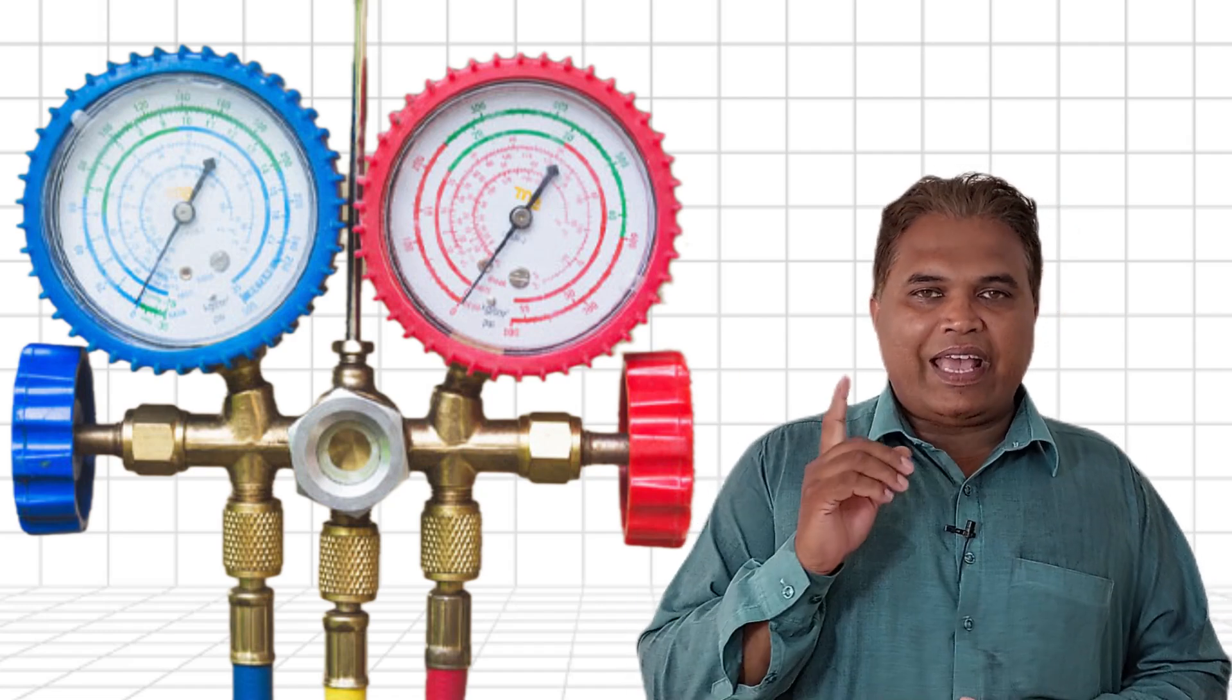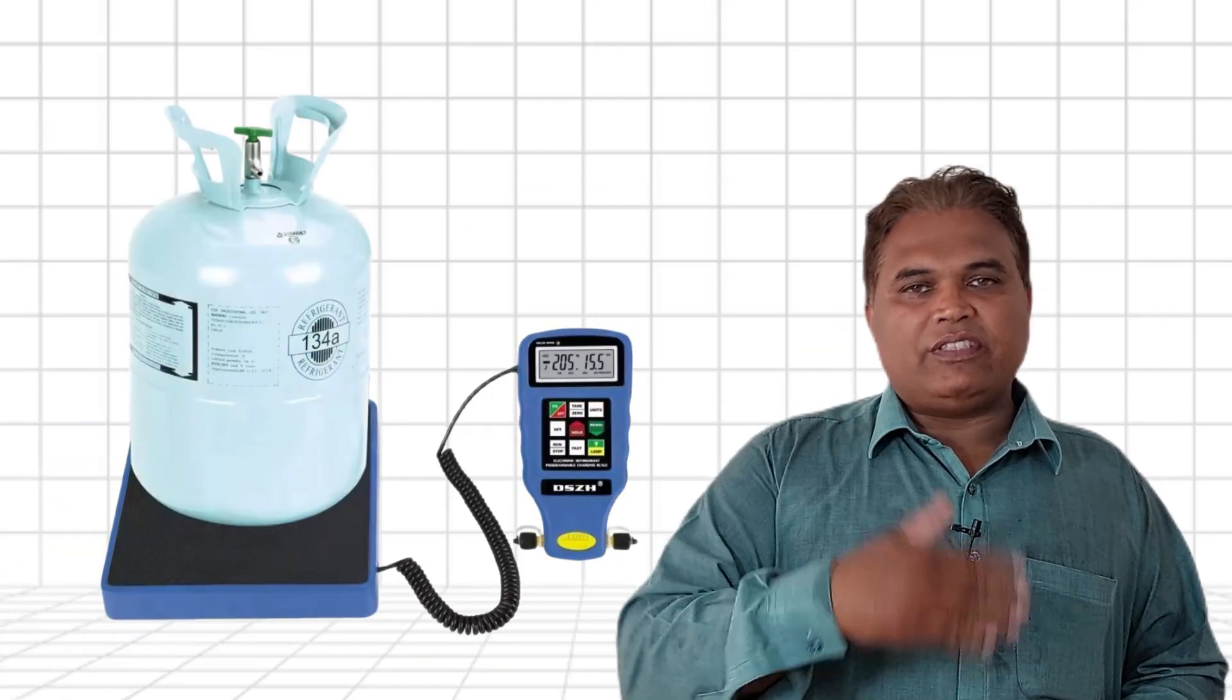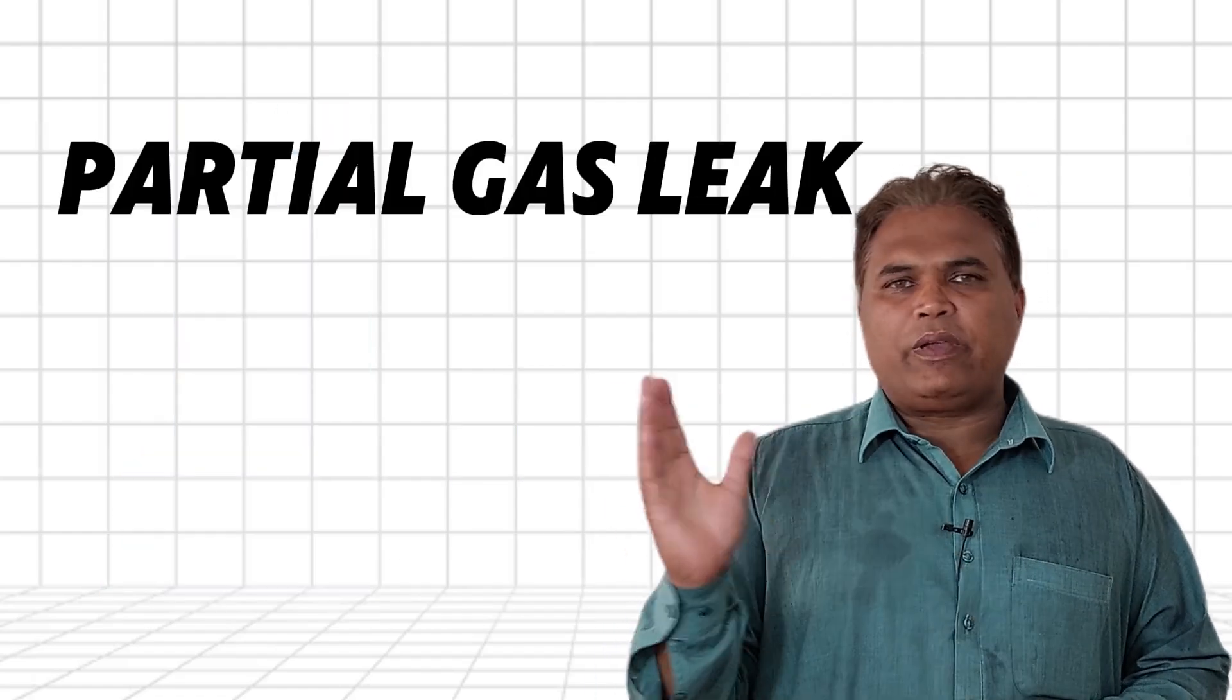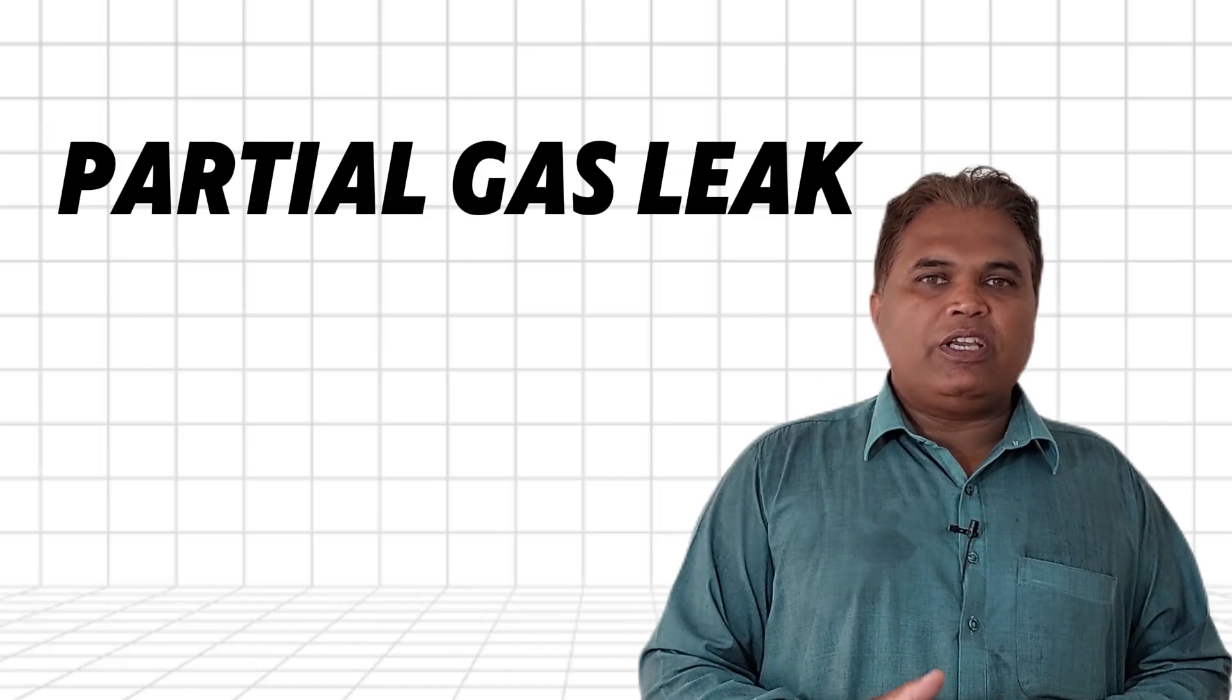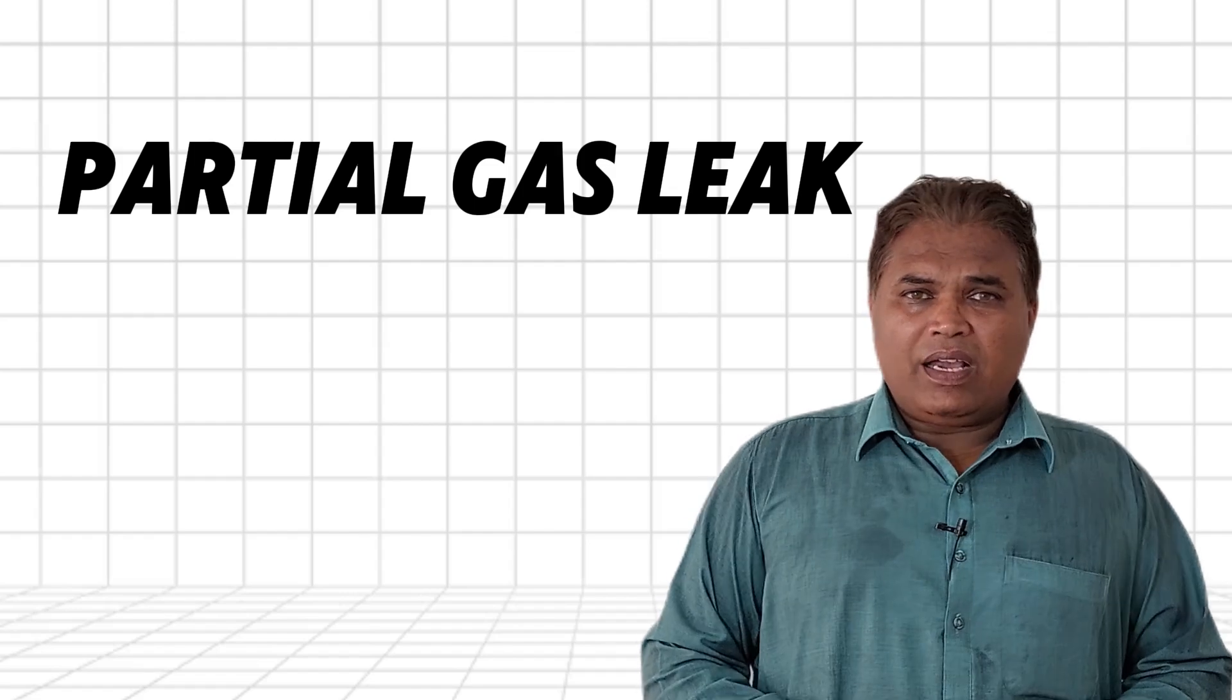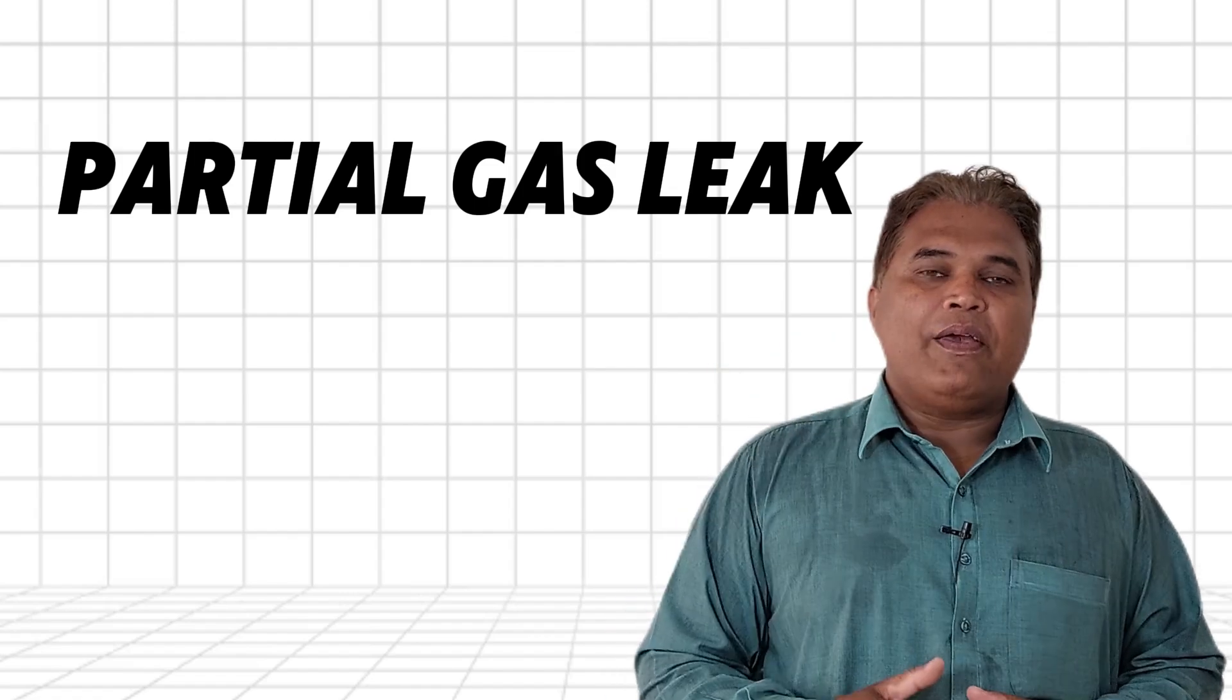For cooling-only models, there are typically two scenarios. If all the refrigerant has leaked out, the system must be charged by weight. Charging by weight minimizes errors and ensures the problem is resolved. For partial gas leak, if some refrigerant is still present and more gas is added without measuring properly, it can result in overcharging, which is another common cause of ice formation on the suction pipe.